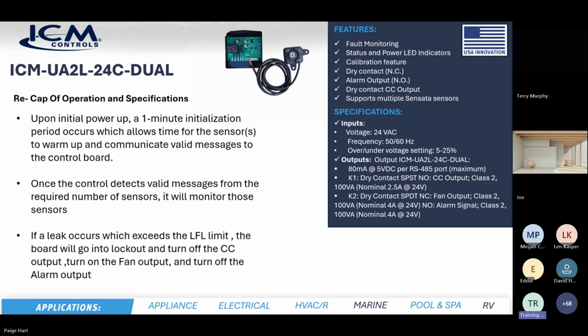But I don't have any specifications on the distance or anything like that. Basically, the guidelines are where refrigerant can collect, and roughly within the distance of the cord that we supply. Basically, this unit features fault monitoring, so it tells you when there's a fault. It has a status LED to tell you when it's an alarm and when it's not an alarm. Calibration features, dry contacts to turn on and off the outputs. And then there's a lot of other electrical stuff that's probably not important for us right here, but those are just some of the other specifications. Basically, you have relays that turn on and off, like turn on the fan when you're in mitigation mode, and turn off the compressor.